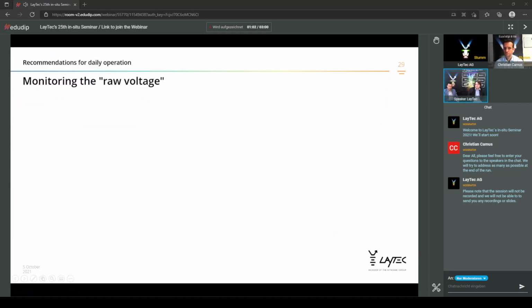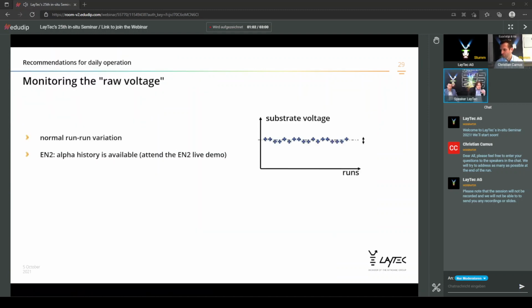Yeah, thank you, Heiko, for showing the typical things we have. We got these reported from the field, from you as the customer. They had trouble with the systems, and what we recommend to avoid such things is very easy: use the raw voltage. The raw voltage is the voltage the detector is showing for the different wavelengths available in the current systems. It's 405 nanometer in the standard system, 633 and 950 nanometer.